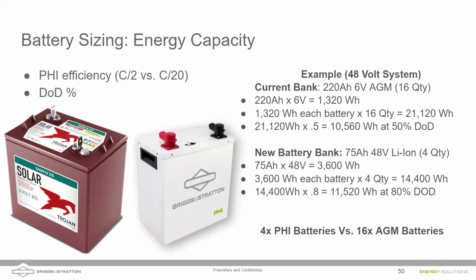Let's get back to sizing. That's a great point. 16 lead acid batteries, probably those Trojan 220 amp hour batteries. A 220 amp hour battery at 6 volts is about 1.3 kilowatt hours worth of storage each. If you got 16 of them, that's about 21 kilowatt hours.